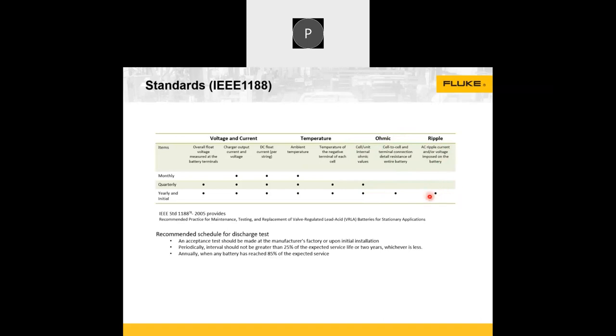This is for 1 year. There are other tests like the charger output, output voltage and current - monthly testing is required, and DC float current is recommended to be tested monthly, and ambient temperature is recommended to be tested monthly. And there are quarterly measurements like the overall float voltage, the current and voltage of charger, then DC float current and ambient temperature, then temperature of the negative pole and cell resistance.